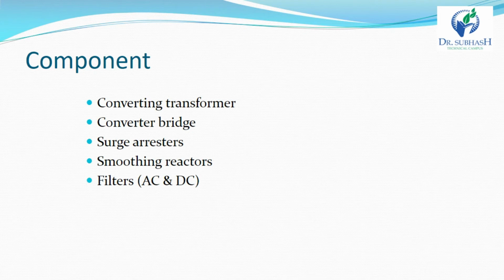Commutation failures in the inverter are prevented by the smoothing reactor by reducing the rate of rise of the DC line current in the bridge when the direct voltage of another series connected bridge collapses. A smoothing reactor reduces the steepness of voltage and current surges from the DC line, and the stress on the converter valves and valve surge diverters is reduced.